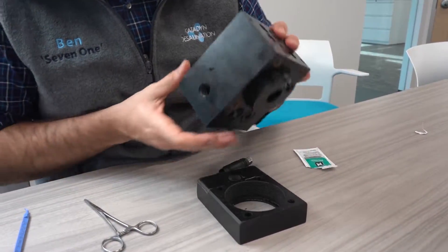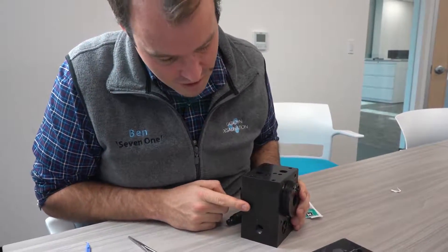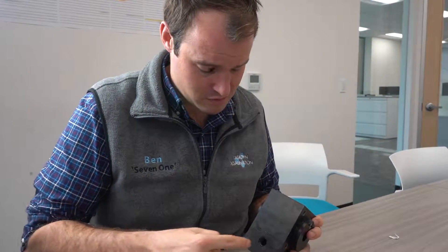Your Clark pump's typically going to be mounted like this with the feed water inlet and the serial number on the front. You'll see that if you have a pre-filter failure, many times when people change their pre-filters, they'll get a little piece of plastic or debris inside that gets past the pre-filters and into the system, going right in there.